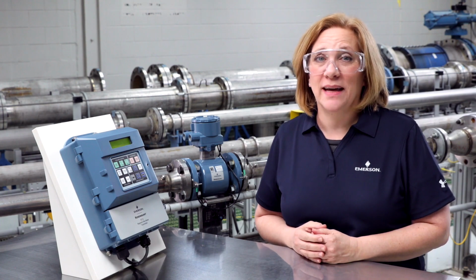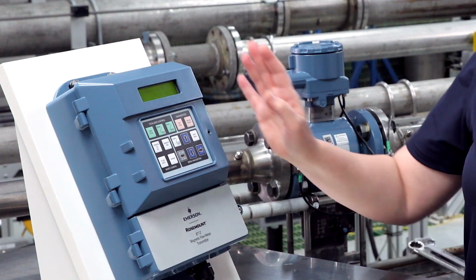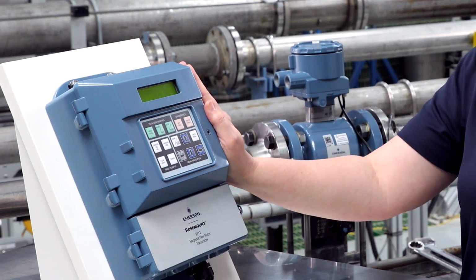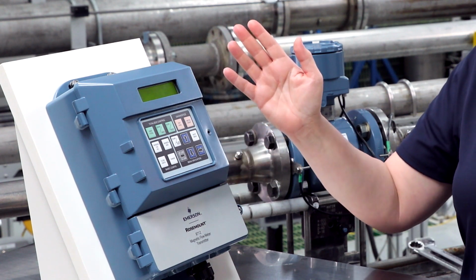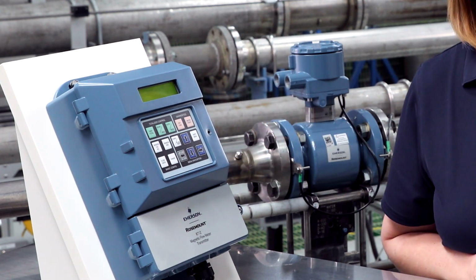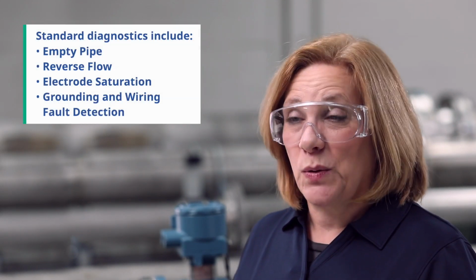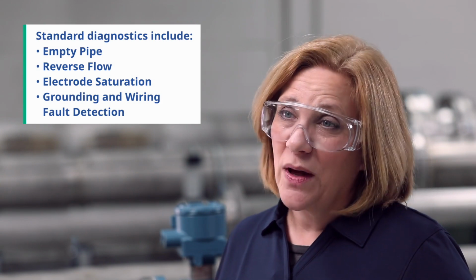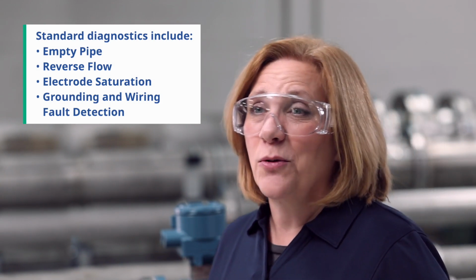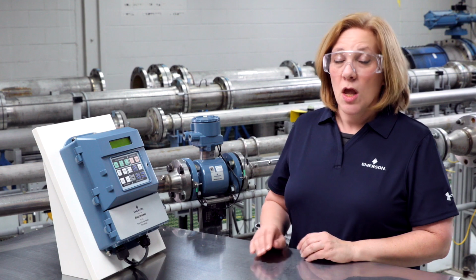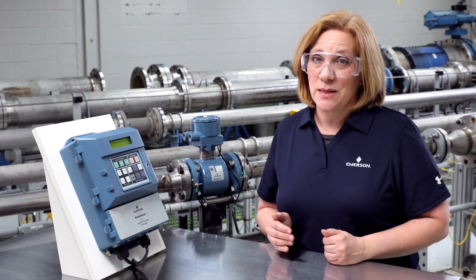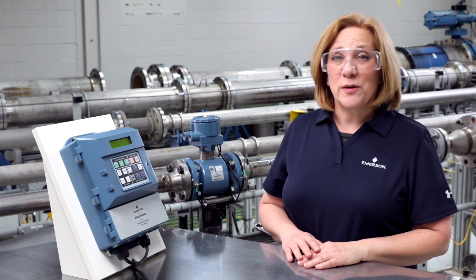I will be reviewing the diagnostic options on Rosemount magnetic flow meter transmitters. I will be showing you on an 8712 wall mount transmitter, but all of our transmitters have the same diagnostic options. Every Rosemount magnetic flow meter comes standard with basic diagnostics. These include empty pipe, reverse flow, electrode saturation, and grounding and wiring fault detection. There are additional licensable diagnostic codes that are available for purchase.